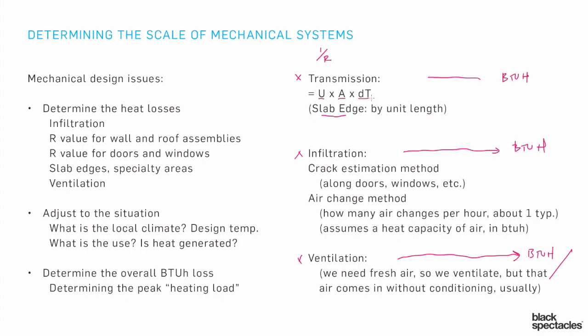These are all based on a specific delta T, so this represents how much the heating system needs to produce at that worst case scenario to maintain the building at 68 degrees or whatever our design temp was. We could choose a higher design temp — it just means the system works harder on cold days. If it got colder outside than expected, say 10 degrees colder due to climate variability, the system wasn't designed for that extra load and would probably dip below our design temp.